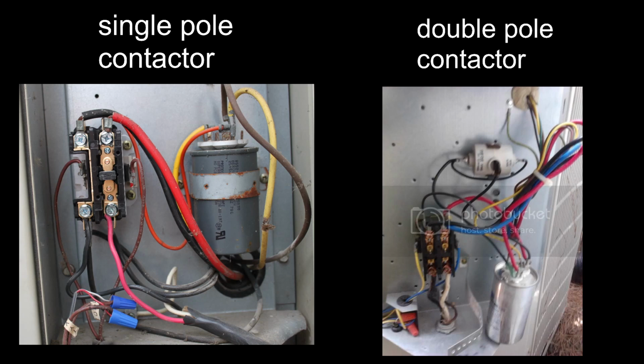So you have three wires off your compressor: your common, your start, and your run. One of those three wires, which is the yellow wire, goes to the capacitor on the right hand side. That's the gray one. There's a yellow wire that feeds off of that. So you see two of them. One's coming from the fan, one's coming from the compressor. Will feed over to a split capacitor, and it usually goes on the hermetic side of the capacitor, which completes the circuit of the compressor.